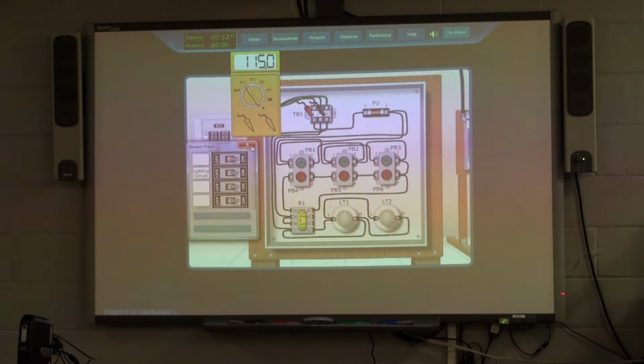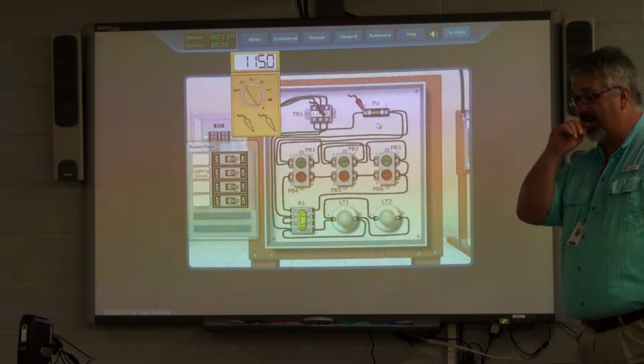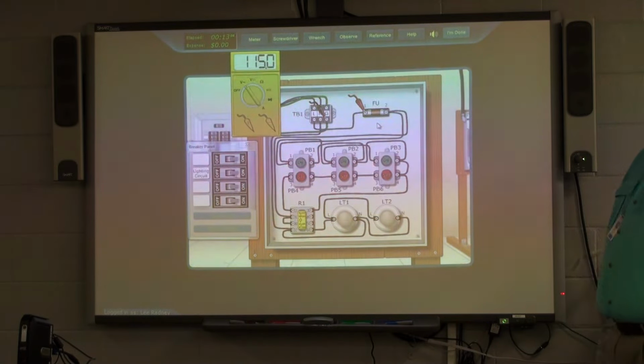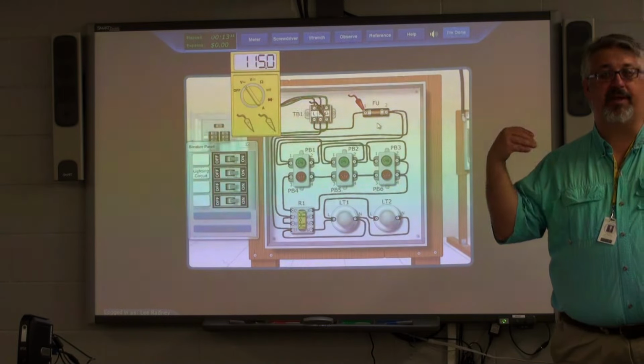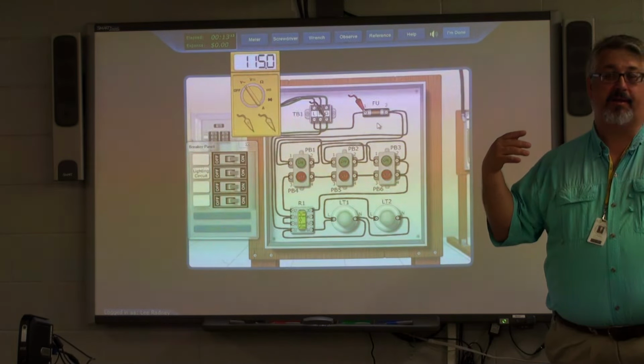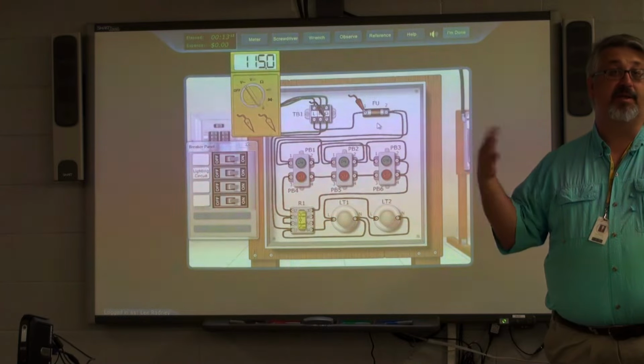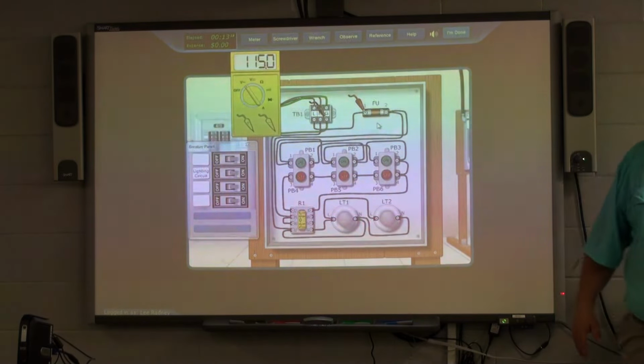What am I going to read if I move my red probe from here to pin 1 of the fuse? Should be 115 volts, right? What about to the other side of that fuse? Still the same—should still be good. It's still the same, unless what? The fuse. Right, if we suddenly change potential on the other side of that fuse, we've either got a connection problem with the fuse block or the fuse is blown. That's the most likely scenario. So yeah, we should have 115 volts there.